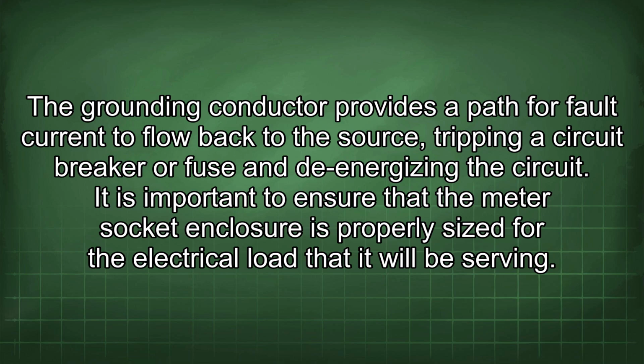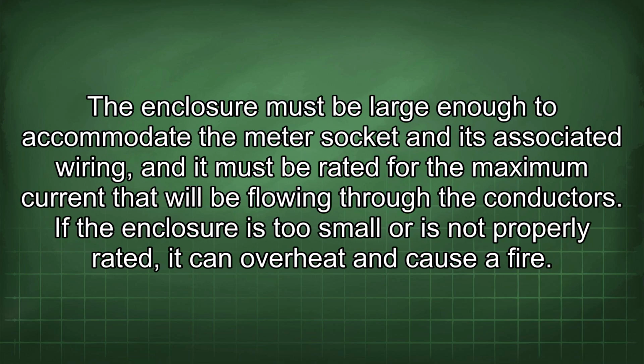It is important to ensure that the meter socket enclosure is properly sized for the electrical load that it will be serving. The enclosure must be large enough to accommodate the meter socket and its associated wiring, and it must be rated for the maximum current that will be flowing through the conductors. If the enclosure is too small or is not properly rated, it can overheat and cause a fire.